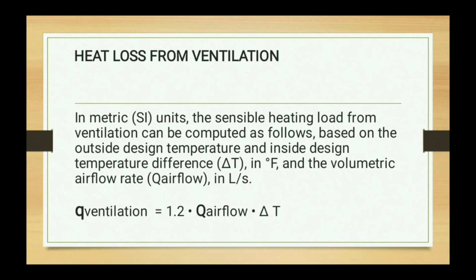In metric SI units, the sensible heating load from ventilation can be computed as follows. Based on the outside design temperature and inside design temperature difference, delta T, and the volumetric airflow rate, ito naman yung formula niya. Ventilation is equal to 1.2 multiplied by airflow multiplied by delta T.